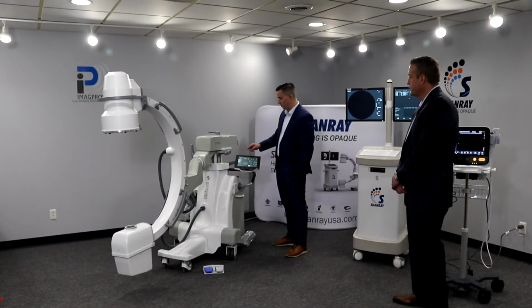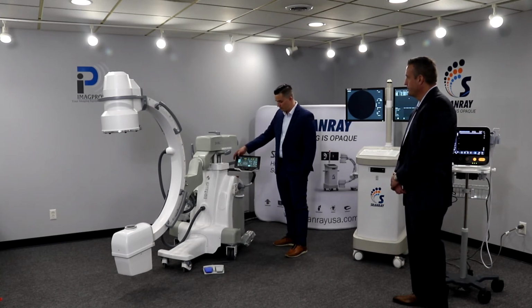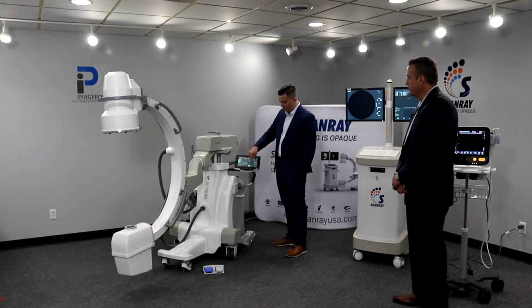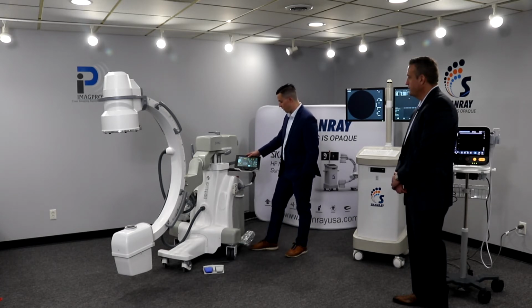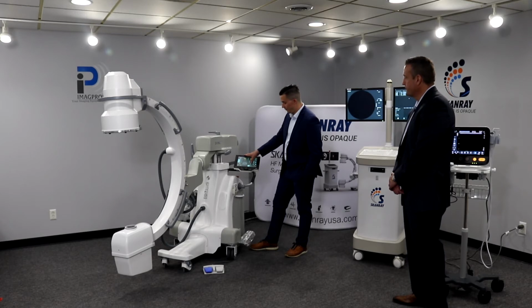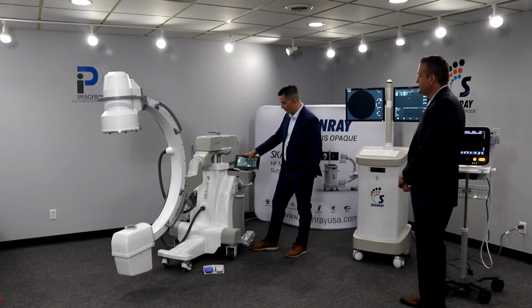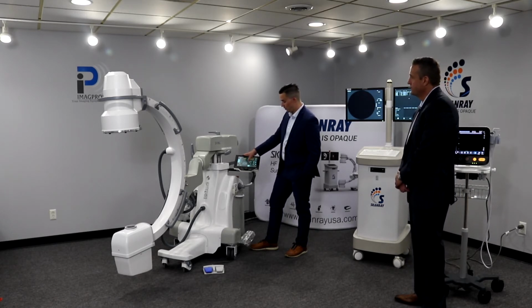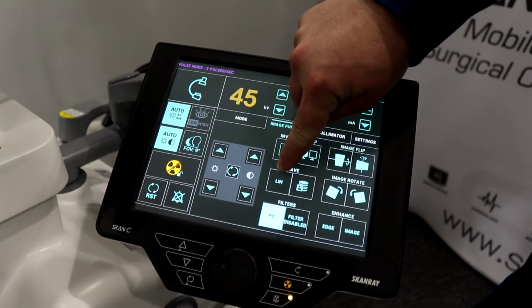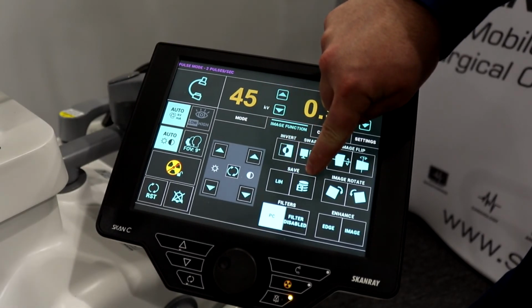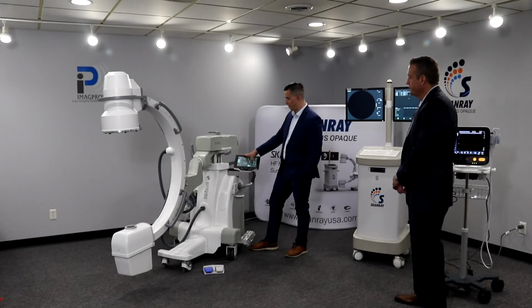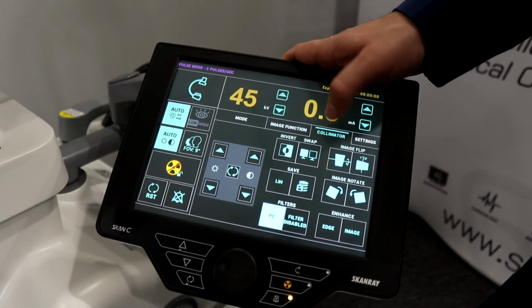90% of what you're going to do is going to be delivered by the auto KV and auto brightness darkness. The remaining 5-10% can be modified by changing how the camera filters work. These are just very minor touches that can be modified at any time. You also have 2 different save buttons: saving for last image hold, which will save the very last frame, as well as this save button, which will save an entire fluoro video. So you can actually save in 2 different methods. Next we have the collimator functions.